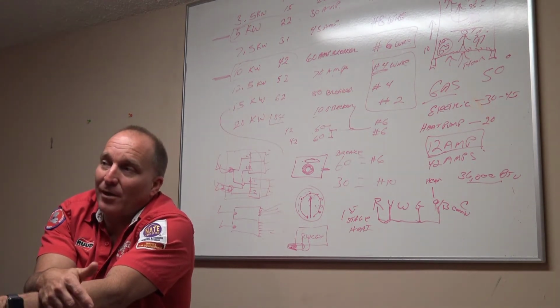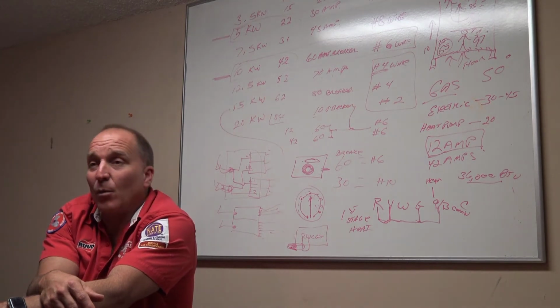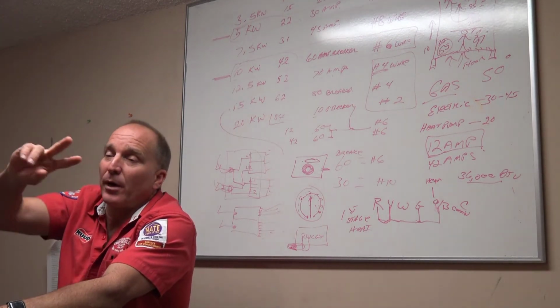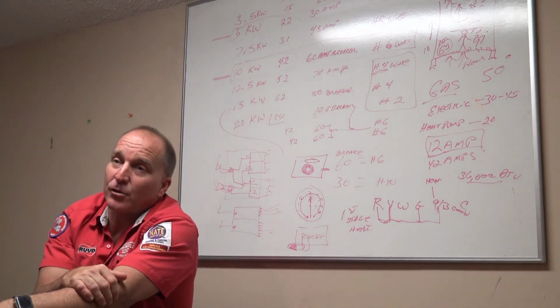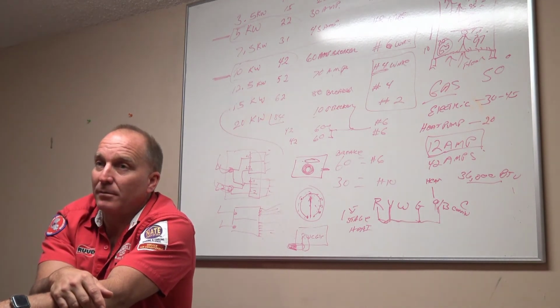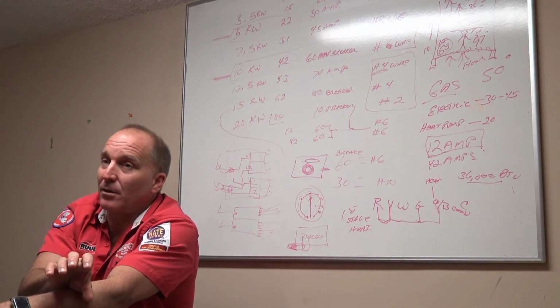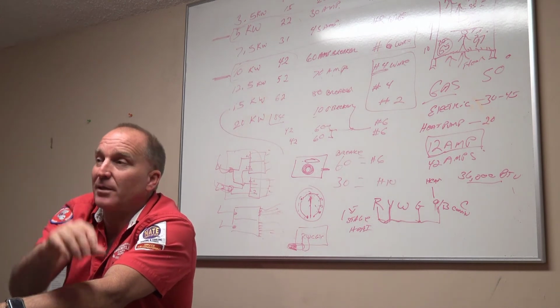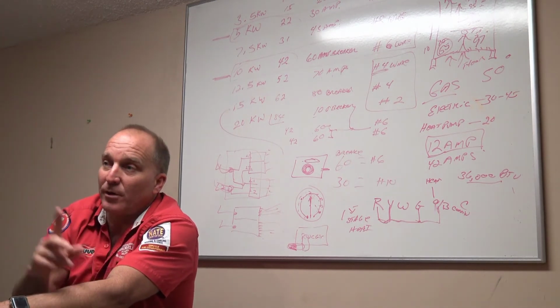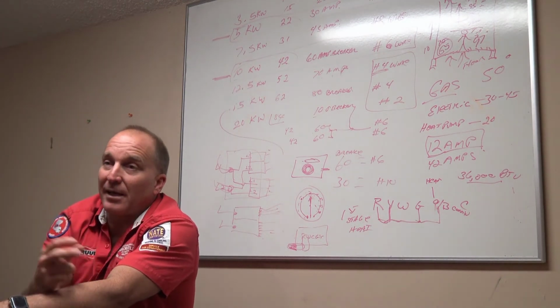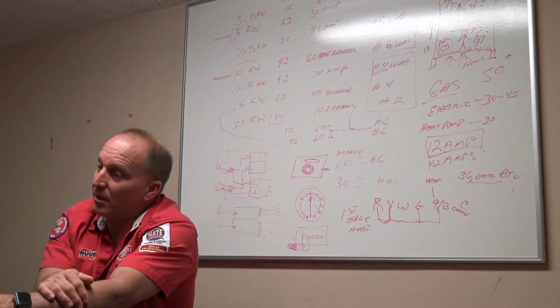I want to make sure that when I do my job, I tell the customer, I moved the breaker to a new space. You need to call an electrician and have him look at your electrical panel, because I moved two or three breakers down and took a different space so I can put my breaker in and you can have heat tonight. I can't put it back in that same space. Okay, but you need to call an electrician.